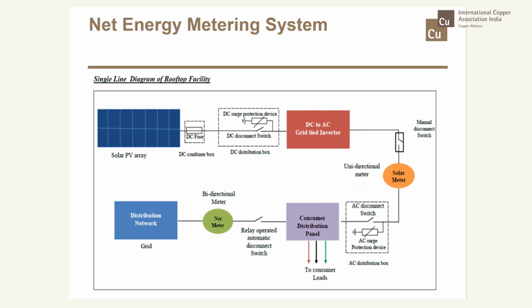And there we have the point of common coupling, where the grid is also interfaced and the load is also connected. And we have a bidirectional meter to measure the power flow in either direction between the PCC and the service connection. So these are the major components, and this is the basic single line diagram of a net metering system followed under a rooftop facility.